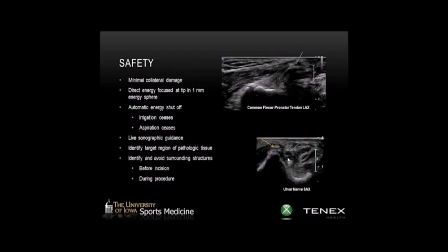And I feel very comfortable about that. There are other safety features, I should say. There's an automatic shutoff, so if your irrigation or your aspiration is stopping and you're not getting good backflow, it will automatically shut off the energy. The biggest safety is really probably the live sonographic guidance.